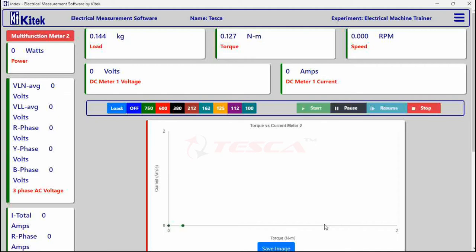And we'll turn on the motor. Then we get the RPMs and torque on the software screen. Increase the RPMs up to 3000 RPMs. Then we gradually increase the excitation to generate the voltages from the synchronous generator up to 400 volts. Right now, no amperes are provided because we have not yet loaded the synchronous generator.